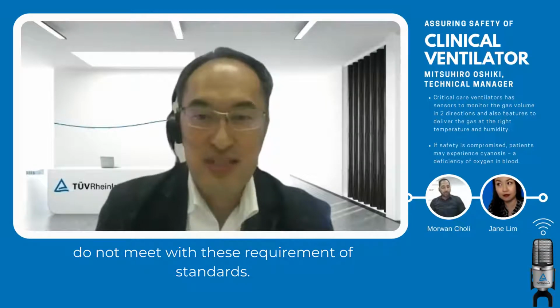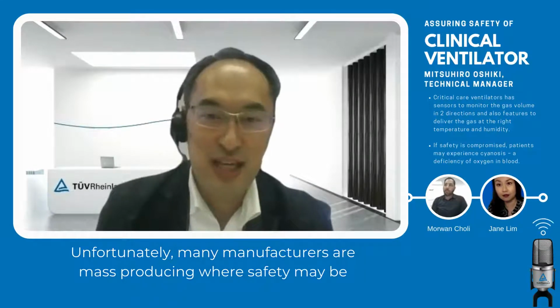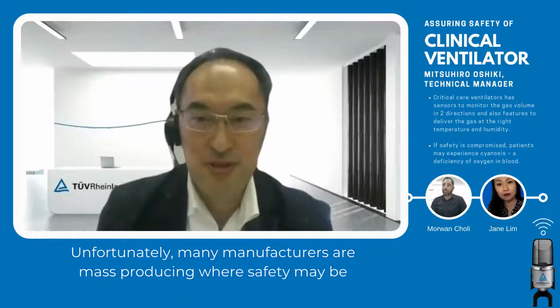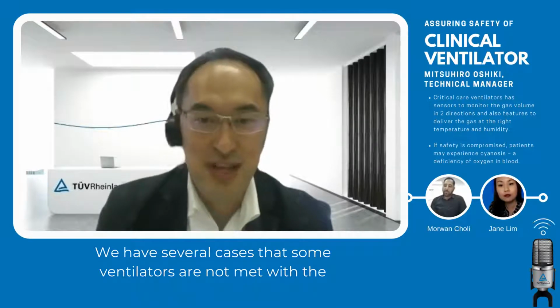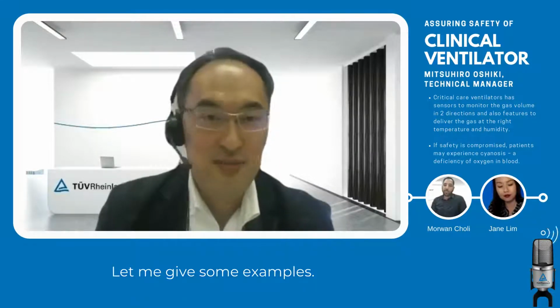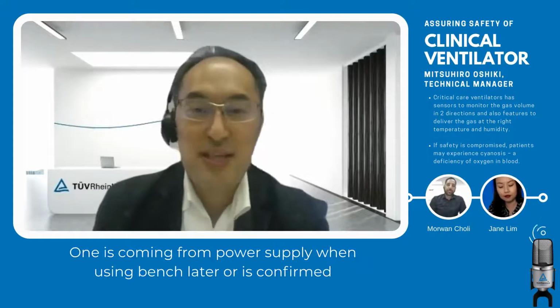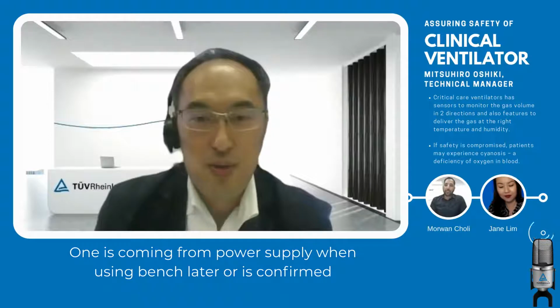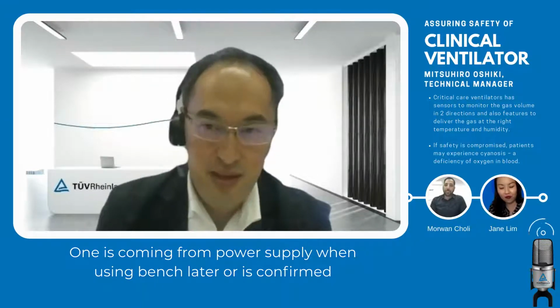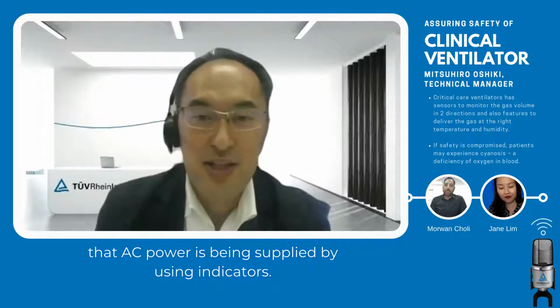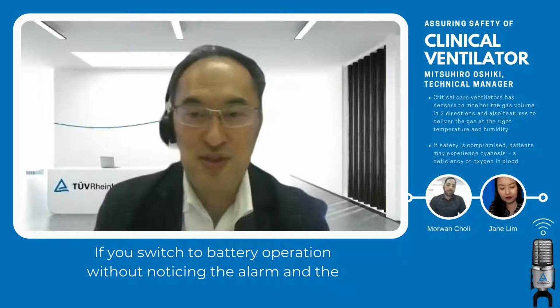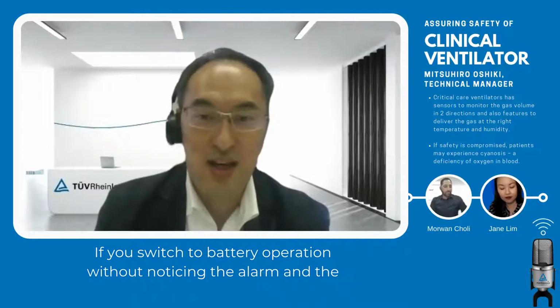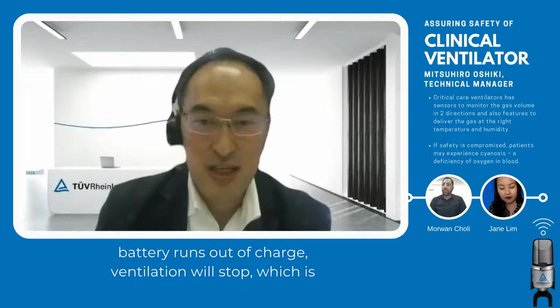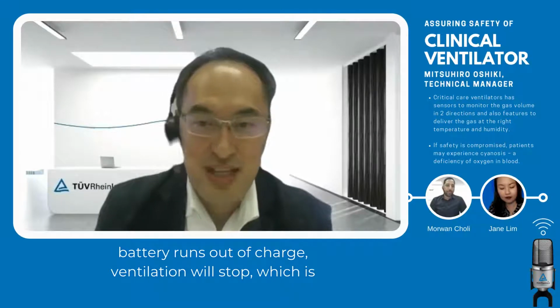Do not meet with these requirements of standards. Unfortunately, many manufacturers are mass producing where safety may be compromised. We have several cases where some ventilators do not meet the requirements of medical practice. Let me give some examples. One comes from the power supply. When using a ventilator, always confirm that AC power is being supplied by using indicators. If you switch to battery operation without noticing the alarm and the battery runs out of charge, ventilation will stop, which is extremely dangerous.